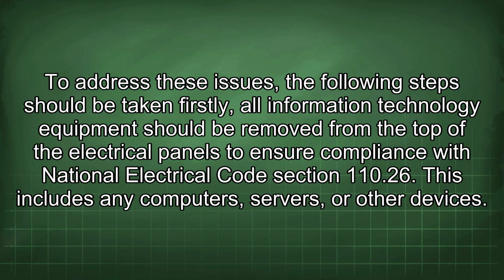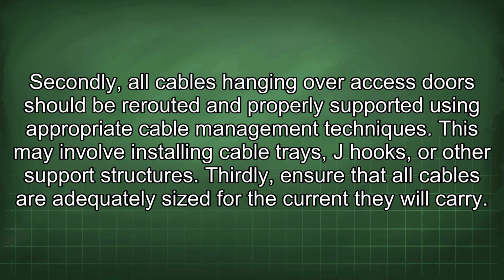Firstly, all information technology equipment should be removed from the top of the electrical panels to ensure compliance with National Electrical Code Section 110.26. This includes any computers, servers, or other devices. Secondly, all cables hanging over access doors should be rerouted and properly supported using appropriate cable management techniques. This may involve installing cable trays, J-hooks, or other support structures.